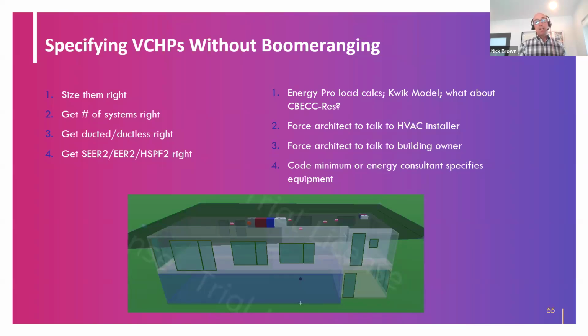It's also important to get ducted or ductless right, because ducted systems require certain verifications, ductless don't. Also important to get the efficiencies right, because if we need an upgraded SEER2 value to get our project to comply, well, that upgraded SEER2 equipment needs to be installed in the field, or now we don't comply anymore.